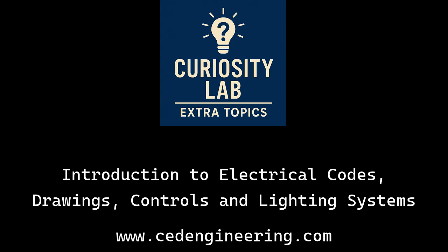Oh, much more. The NEC's main job, and it says this right in Article 90, is protecting people and property from electrical hazards. We're talking shocks, heat causing fires or equipment damage, dealing with overcurrents, fault currents, all that dangerous stuff. It establishes a baseline, a minimum standard. It's not focused on convenience, really, or making future expansion easy. It's about a predictable, safe level. And it aligns with international standards, too, like the IEC. Shows a global agreement on these basic safety ideas.